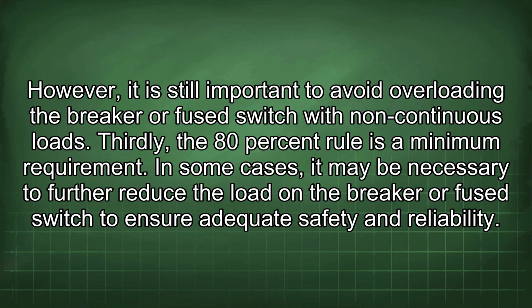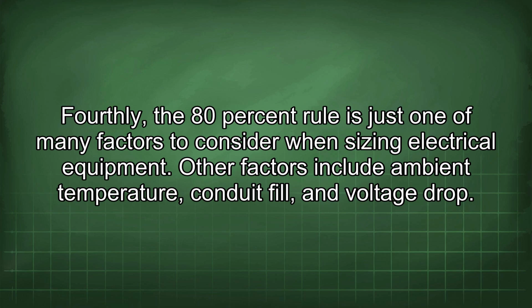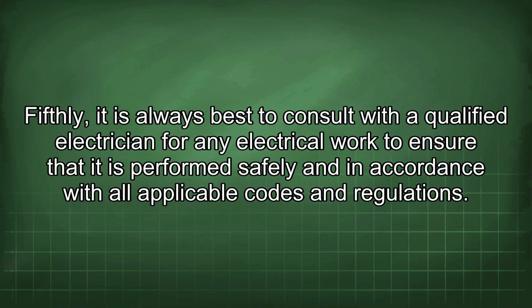Thirdly, the 80% rule is a minimum requirement. In some cases, it may be necessary to further reduce the load on the breaker or fuse switch to ensure adequate safety and reliability. Fourthly, the 80% rule is just one of many factors to consider when sizing electrical equipment. Other factors include ambient temperature, conduit fill, and voltage drop. Fifthly, it is always best to consult with a qualified electrician for any electrical work to ensure that it is performed safely and in accordance with all applicable codes and regulations.